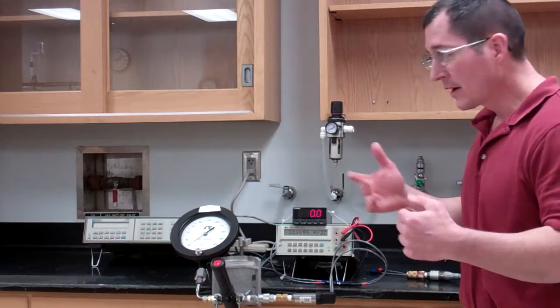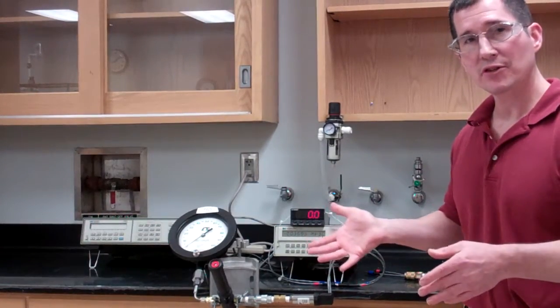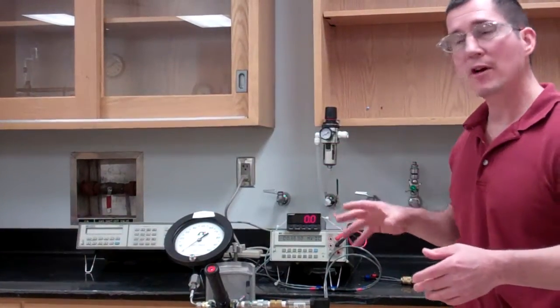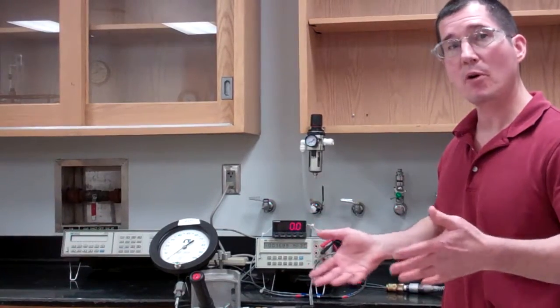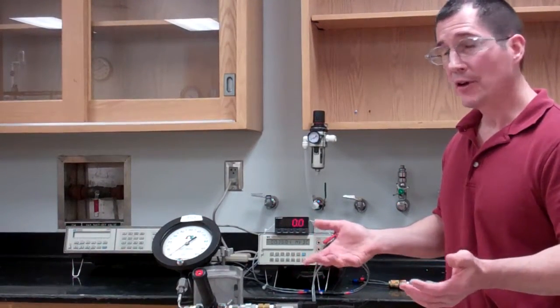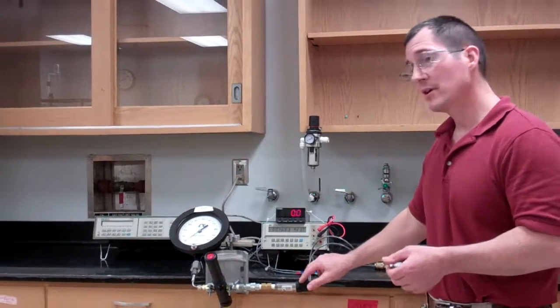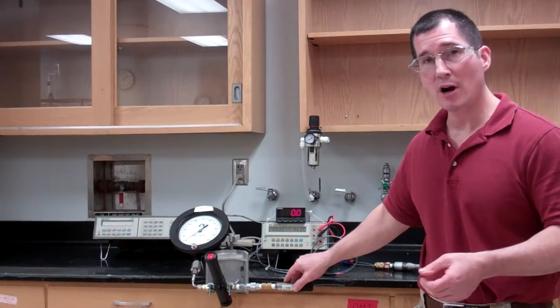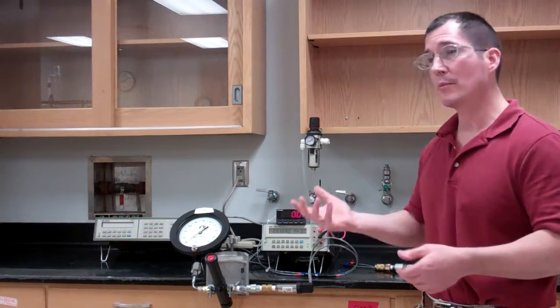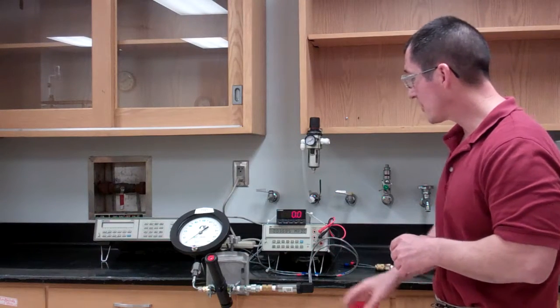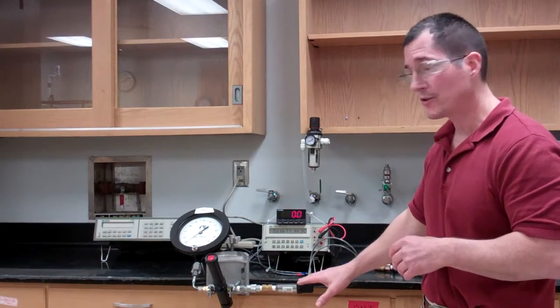Well, if you're having a problem with the control system, you need to check all the components of the control system to see which part may be the problem. So if the measurement sensor is not functioning properly, then the signal going to the controller is not going to be correct, and then the signal from the controller to the final control element is not going to be correct, and that could be your problem. Or the problem could be your final control element, or it may be your controller itself. So you have to investigate all the parts of it. So here we're going to look at the input sensor.